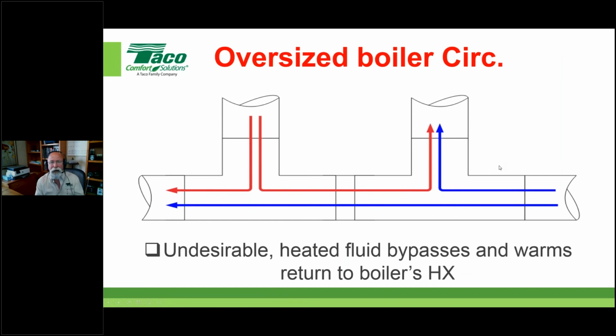Here's what we don't want to happen, the thumbs down. This shows that if I oversize the boiler circulator, I have more flow going back across here, blending that cooler water with the heated water, and now I'm reducing the overall boiler efficiency and the overall system efficiency. So that's undesirable.